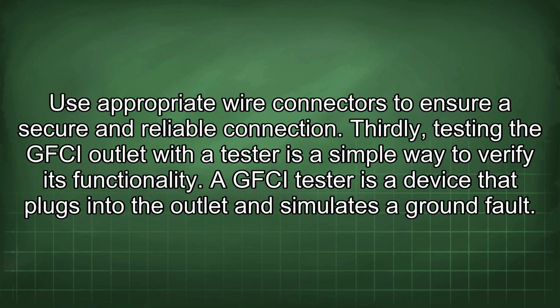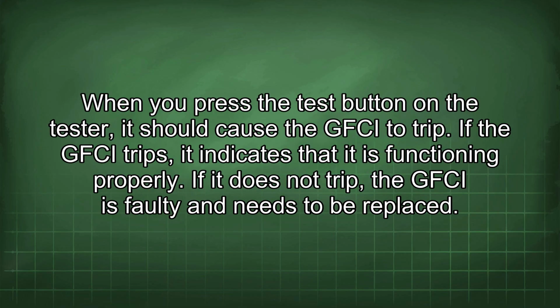Thirdly, testing the GFCI outlet with a tester is a simple way to verify its functionality. A GFCI tester is a device that plugs into the outlet and simulates a ground fault. When you press the test button on the tester, it should cause the GFCI to trip. If the GFCI trips, it indicates that it is functioning properly. If it does not trip, the GFCI is faulty and needs to be replaced.